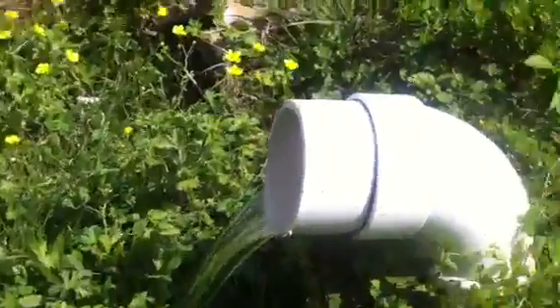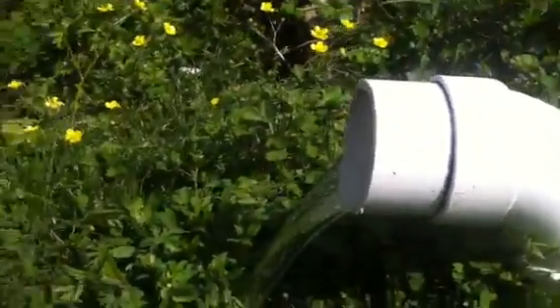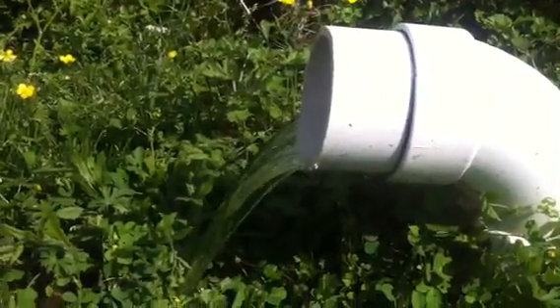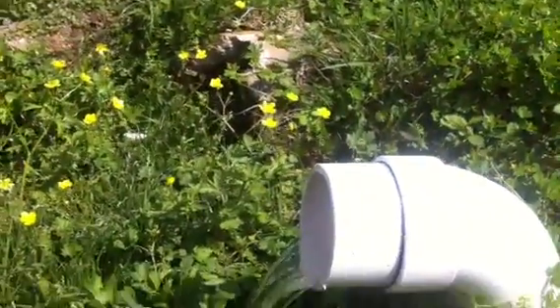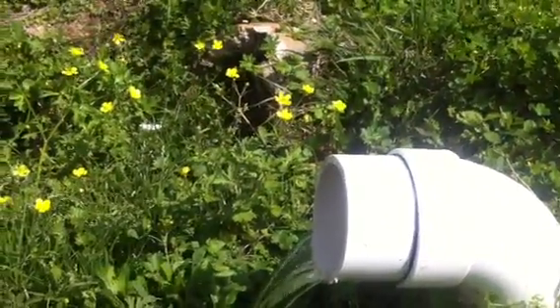This is our effluent coming out, and here it is going to our ditch, and it's fresh, clear. I don't know whether it's like a forest rain, but it sure looks great. That is the effluent quality coming out at a nice controlled rate. It trickles on down through vegetation and on out to our ditch, by far exceeding our design requirements here at this plant, which is 30/45.